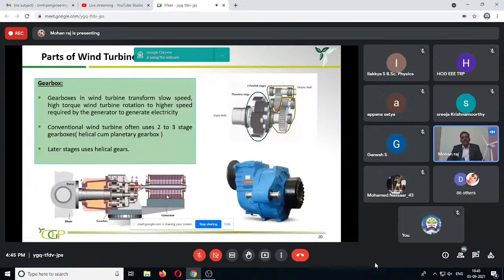Okay, so next, the gearbox and the geared wind turbine. This gearbox is converting the slow speed, high torque wind turbine rotation to the higher speed required by the generator to generate electricity. In wind turbines, on the next slide we are going to see the generator also. The induction generator is used to generate the electricity. So for an induction generator, for a 4-pole or 6-pole generator, the 4-pole generator synchronous speed is 1500 RPM.